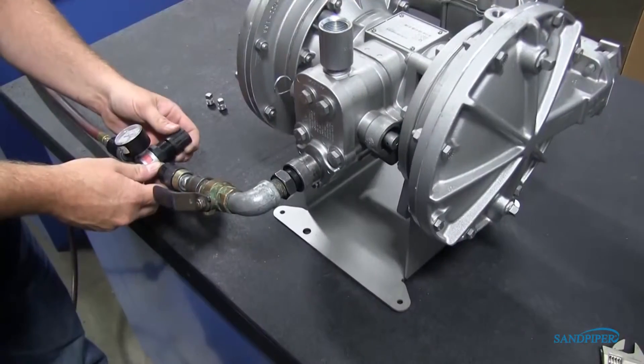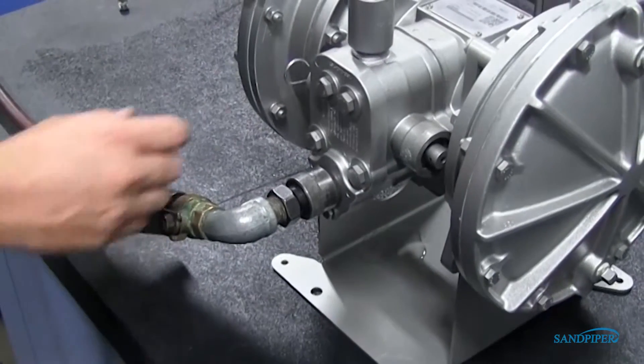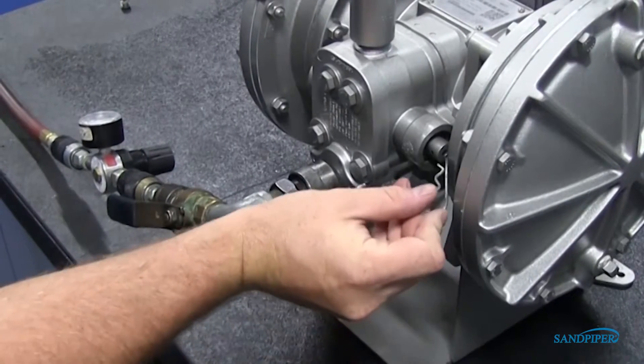Release all air pressure to the pump and remove the safety clip. The diaphragm will relax and will come to center. Watch the loose pipe plug closely as air escapes and the driver fluid level rises.